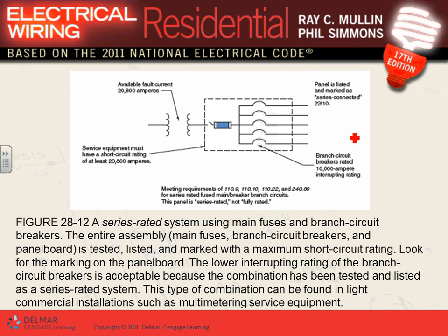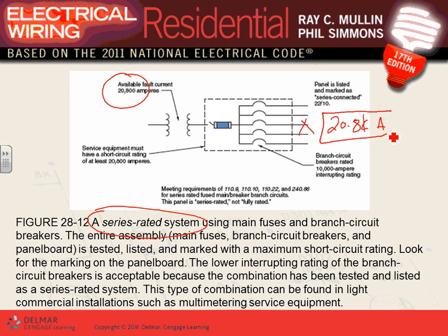Now, series rated: I have a 20,800-amp available short circuit. The main is rated for 22,500 amps, but all the branch circuit breakers are rated for only 10,000 amps. They call it series rated coordinated — the manufacturers test these circuit breakers and fuses together. By design, if the short circuit exceeds what the branch breakers can handle, they hold and let the main take care of business.